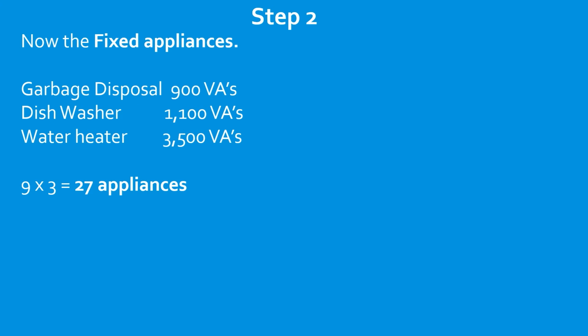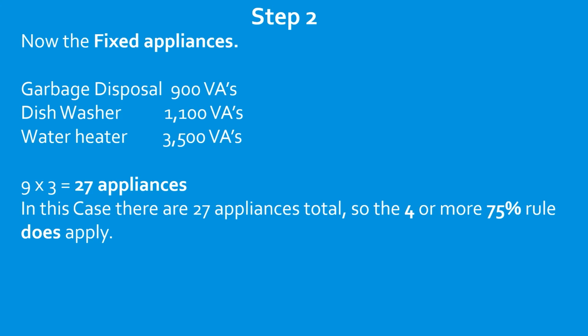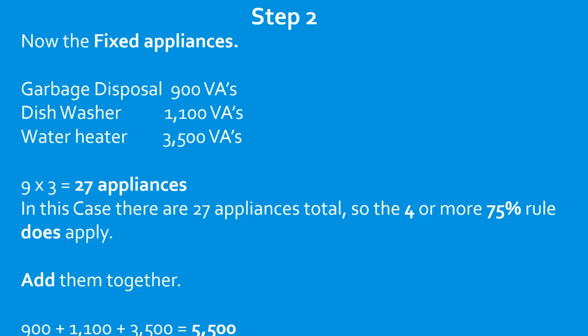Now we go for our fixed appliances. So our garbage disposal, dishwasher, and water heater, although it is only 3 appliances per unit, we are doing it on the whole service or feeder. So we have to treat the 4 or more 75% rule here. So we take our 9 units multiplied by 3 appliances per unit. That's going to give us 27 appliances. In this case, there's 27, so this rule does apply. You just add them together first. That's going to give you 5,500 VAs. Now, you're going to multiply that by 9 units and by the demand factor. So 5,500 multiplied by 9, multiplied by 0.75, and that's going to give you 37,125 VAs.